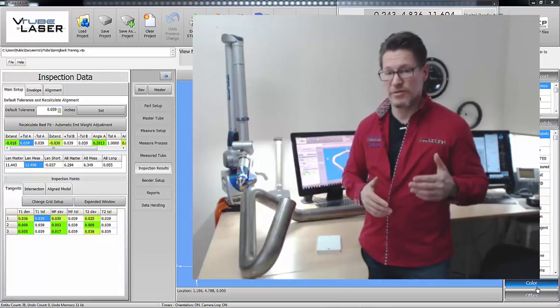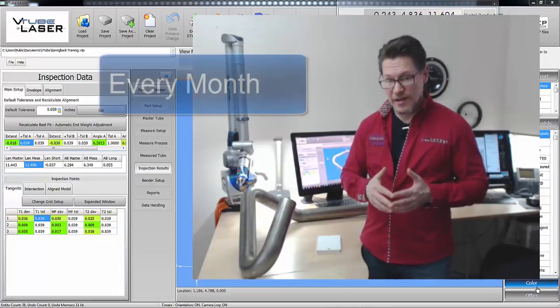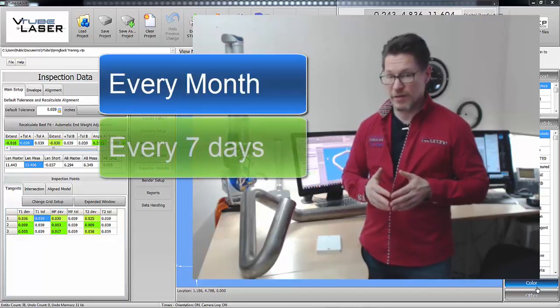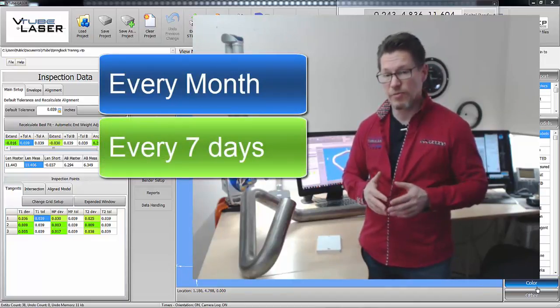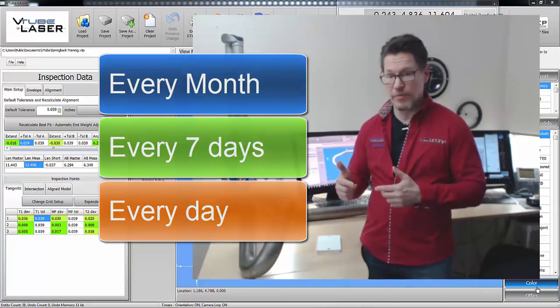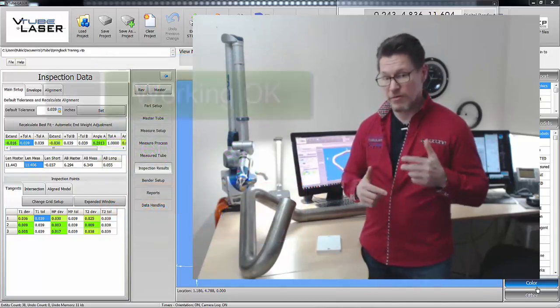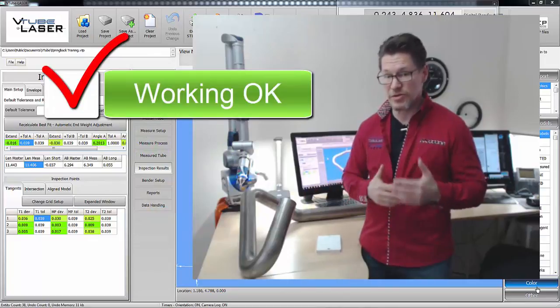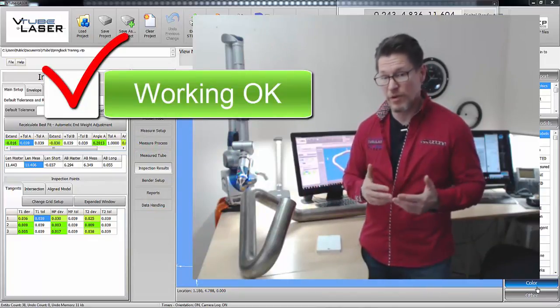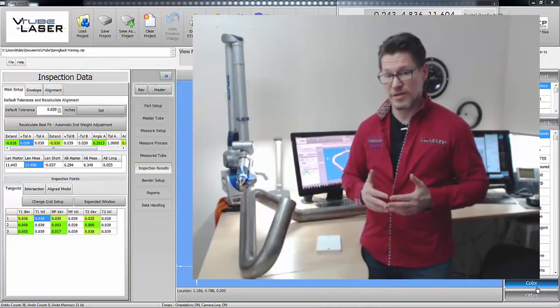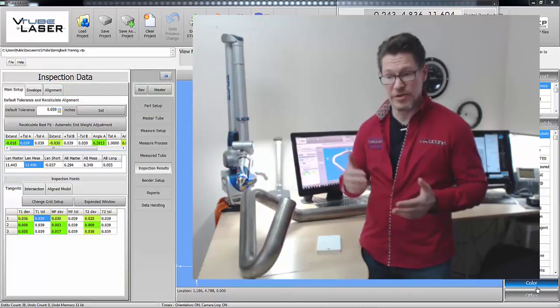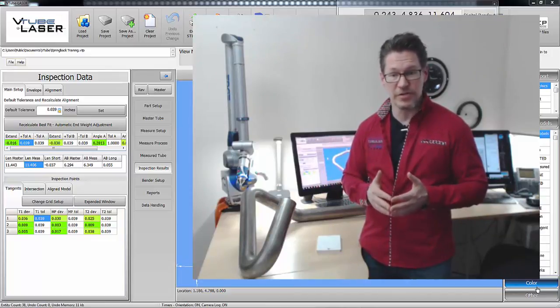The second point is this. FARO recommends that you calibrate the probes and scanners at least once a month. Some of my customers, however, like to calibrate a lot more often, and here's why. Every time you perform a calibration of a probe or a scanner, you're cross-checking the entire system to make sure that it's actually functioning the way it should. FARO makes the qualification process for calibration of the probes and the scanners very strict. So that's a good way to check to make sure your arm is functioning as it should before you use it that day.